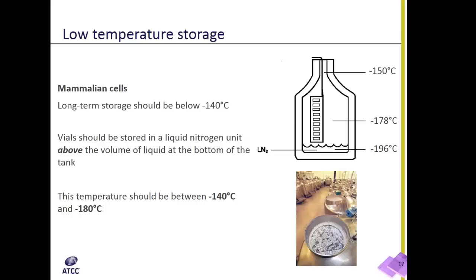Vapor phase systems create a vertical temperature gradient within the container. At the bottom, the liquid nitrogen will maintain a temperature of around minus 196 degrees Celsius. The temperature of the vapor phase decreases as it reaches the top portion of the container.